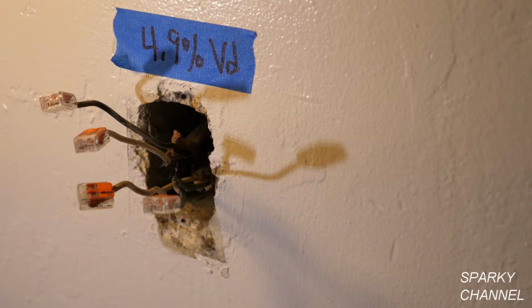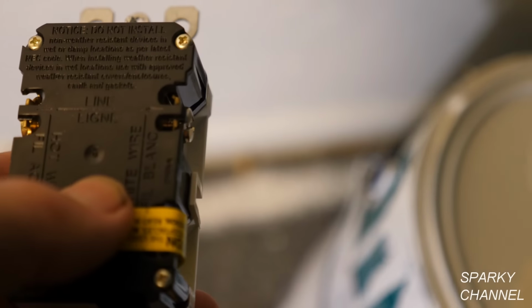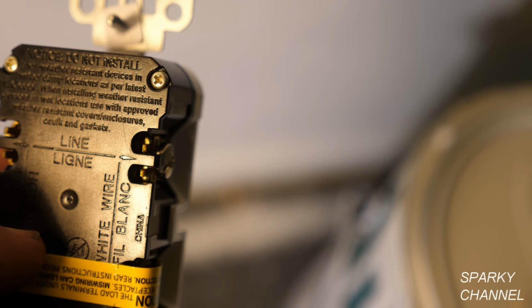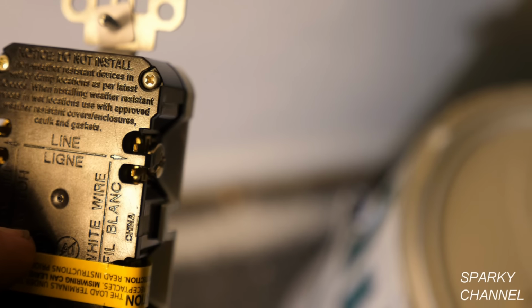I'm double checking. On the back of the GFCI, you'll see it clearly designated where the line cable goes. So your hot line wire is going to go to this brass colored screw, and that aligns with the short slot on the receptacle. So we've got the brass colored line for the hot, and then for this side, this is where the neutral goes. You see there's a silver screw right there, and that aligns with the long slot.